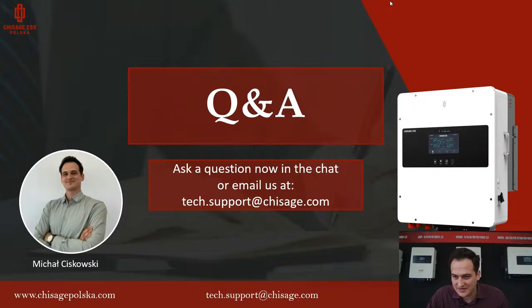Smart load, fine, and backup. Yes, but you have to remember that you cannot put the smart load at 14 kilowatts and the backup at 14 kilowatts together, because that is 28 kilowatts of power. So we cannot do this. It has to sum up to the power of the inverter. So for a 14 kilowatt inverter, the sum of the backup load and smart load has to be 14. It cannot go higher than this.